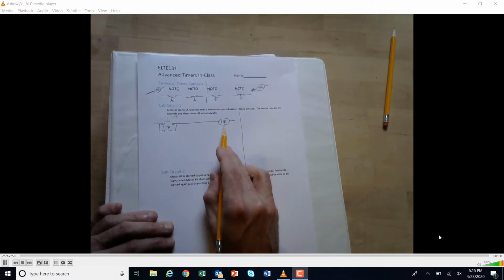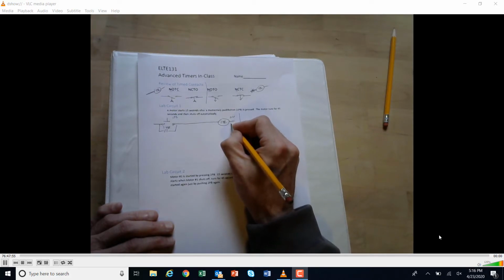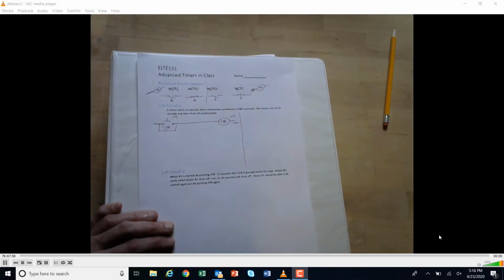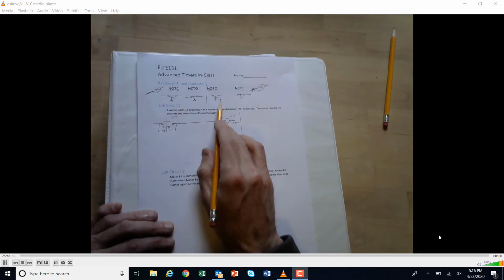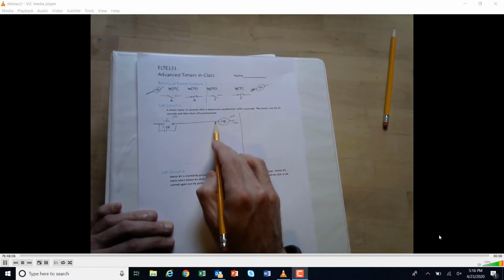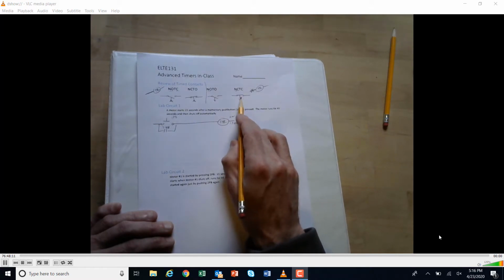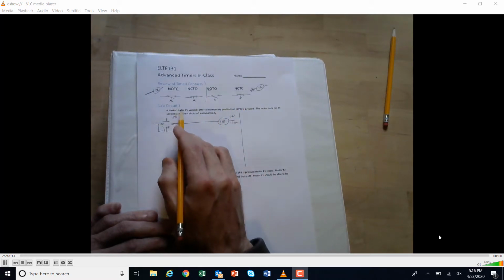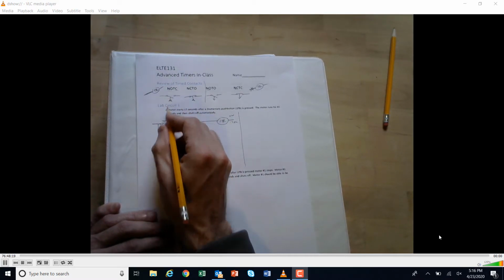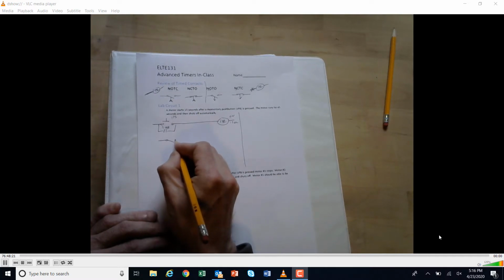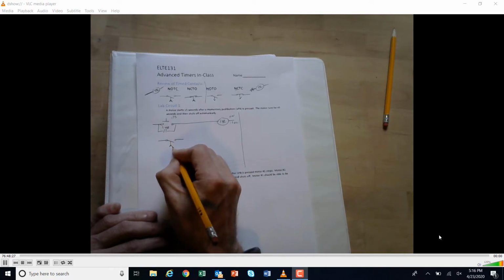So I push this and I turn on this timed relay. I'm going to make this an on delay relay, and I'm going to set it for 15 seconds, okay? So then after 15 seconds, what do I want to occur here? By energizing this, would I want this to close and then open, or would I want this to open and then close? Well, because it's an on delay here, I think I want this to start open, and then after 15 seconds, I think it should close.